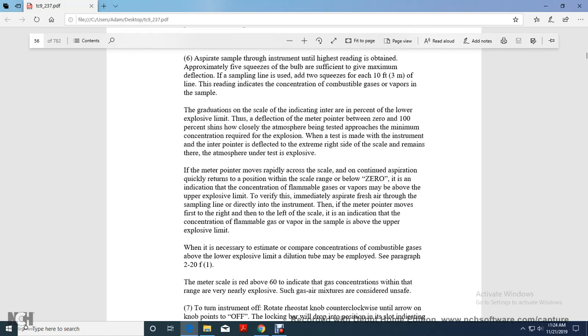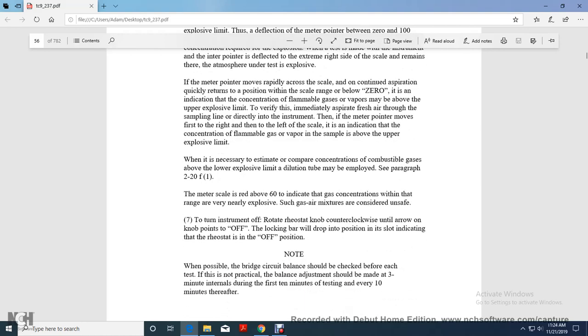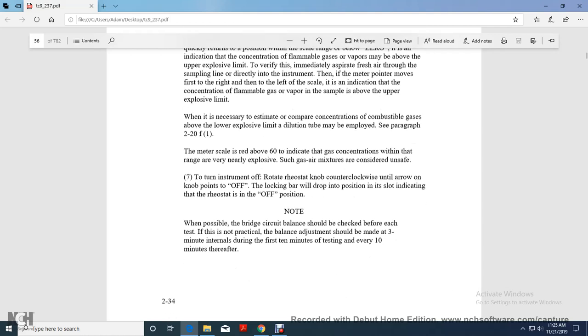When a test is made with the instrument and the pointer deflects to the extreme right side of the scale, the atmosphere under test is explosive. If the meter pointer moves rapidly across the scale and, with continued aspiration, quickly returns to a lower position, the concentration of flammable gases and vapors may be above the upper explosive limit. To verify, immediately aspirate fresh air through the sampling line directly into the instrument. Then if the meter pointer moves to the right and then to the left of the scale, this indicates that the concentration of flammable gas or vapor in the sample is above the upper explosive limit.